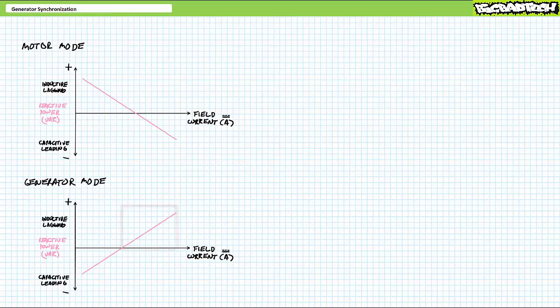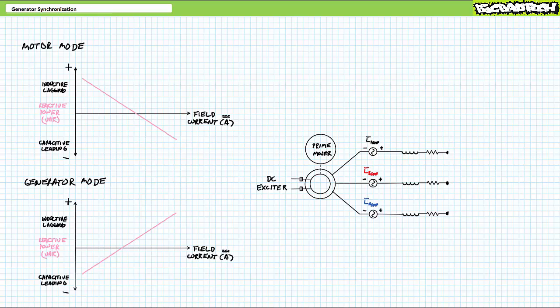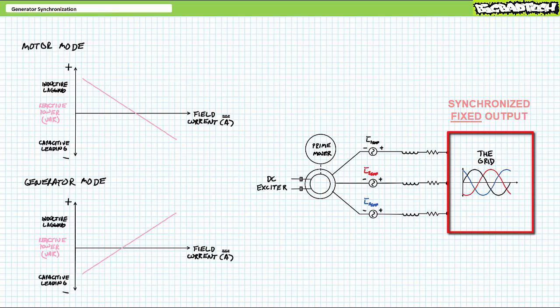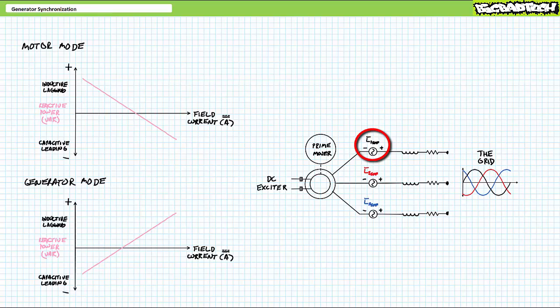It deals with a simplified model of a generator winding employed in the Loaded Synchronous Generators lecture, available at the Big Bad Tech channel. This simplified model employed a voltage source resulting from the generator electromotive force in series with a small resistor and comparatively larger inductive reactance. If isolated from the grid, adjusting field current directly affected output voltage magnitude at the terminals of the generator. However, once synchronized to the grid, the voltage of the output terminals of the generator would remain fixed by grid-imposed voltage. Any adjustment to the field current after synchronization affects the generator electromotive force only, thus controlling the degree of differential between the generator EMF and grid voltage, thereby affecting the current flow through the resistive and reactive components internal to the winding. Thus, in underexcited conditions current leads voltage, and in overexcited conditions current lags voltage.